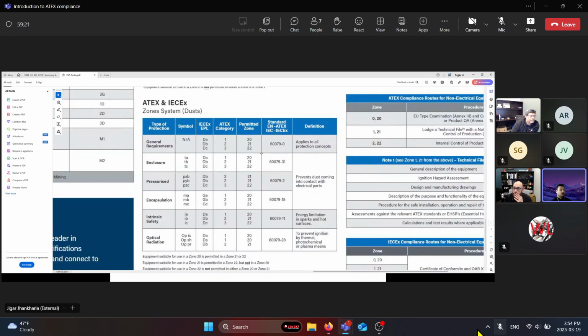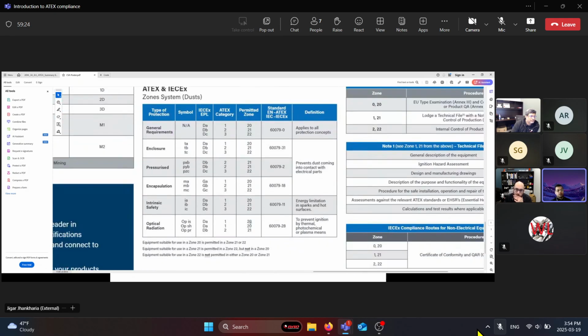Optical radiation in the dust environment is for zone 20 and zone 21. Again, it would not apply to your product. So for you to achieve zone 21 and zone 22, that's something you would have to discuss internally, if you want to redesign your product with intrinsic safety as a method of protection. Then that's one way you can meet the requirements of zone 20 and zone 21, or zone 21 and zone 22, or have the full device enclosed.